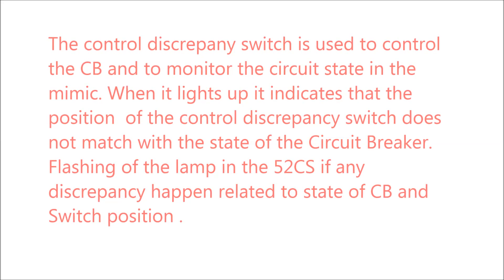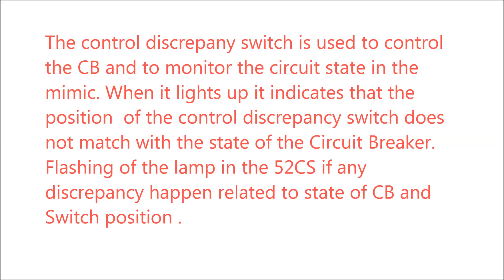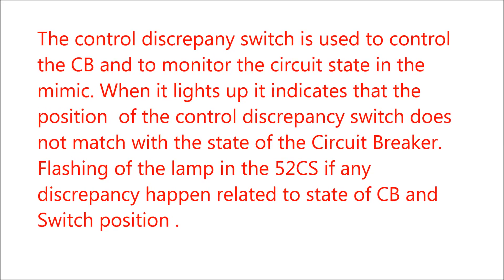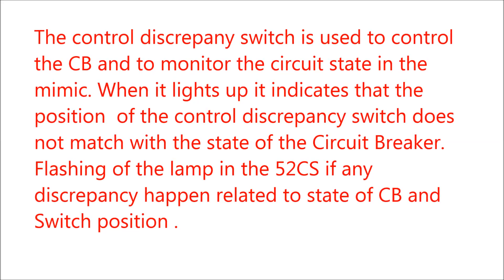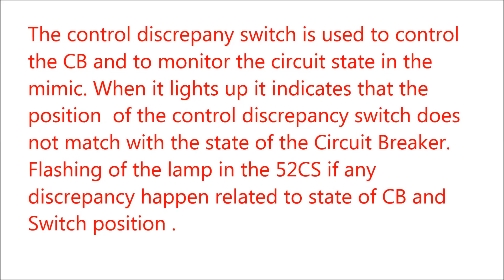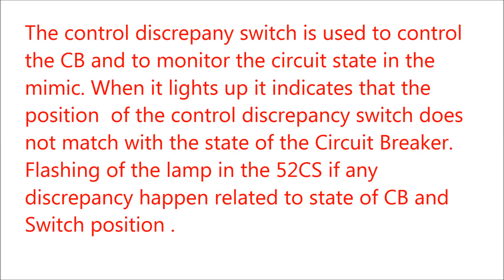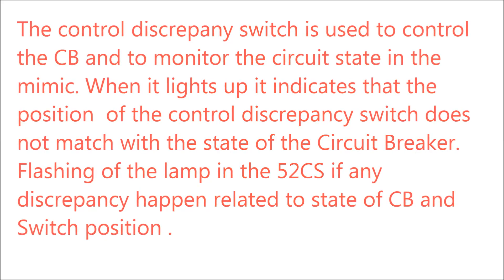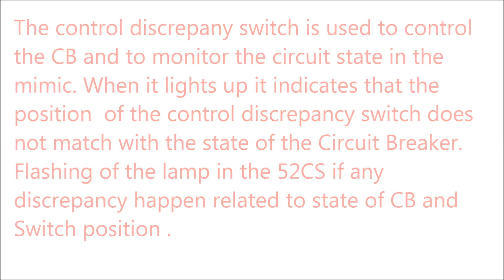When it lights up or illuminates, it indicates that the position of the control discrepancy switch does not match with the state of the circuit breaker. Flashing of the lamp in the discrepancy type control switch occurs if any discrepancy happens related to the state of the CB and the switch positions.